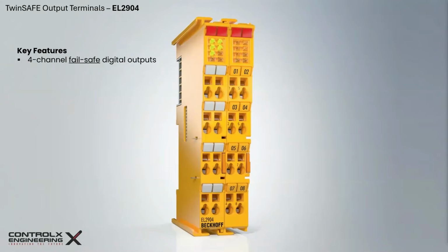Fail-safe means that the terminal will automatically switch off if it detects any kind of internal or external fault. The EL2904 is designed to switch 24-volt DC loads up to half amp per channel. While that might seem low, remember that these aren't meant to power a massive actuator directly. They are meant to drive the STO or safe torque off inputs of a VFD or the coils of safety contactors.